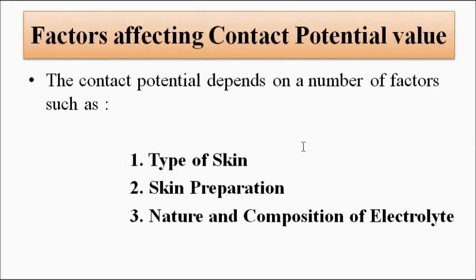The factors which affect the contact potential are: the type or nature of the skin — whether it is dry or moist, and whatever other skin properties exist best known to medical professionals. Then there is skin preparation — how the skin is prepared for measurement before the measurement is done, and how the electrode is placed. The other factor is the electrolyte or electrode paste or jelly used to achieve adhesion. These are the factors that affect the contact potential value.